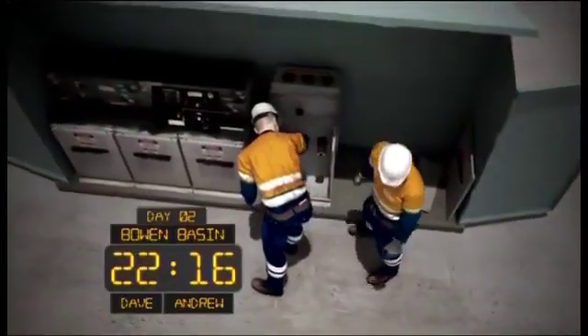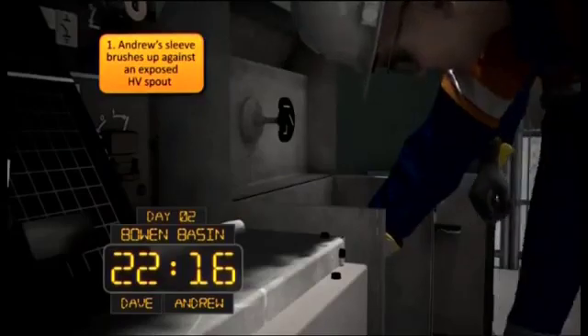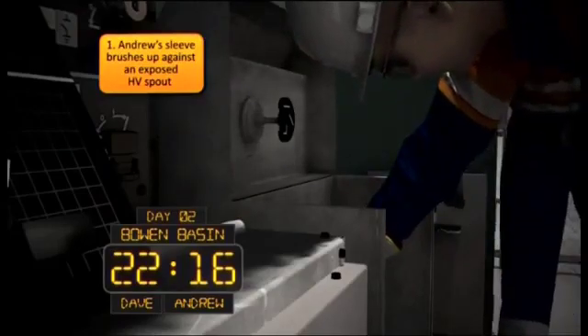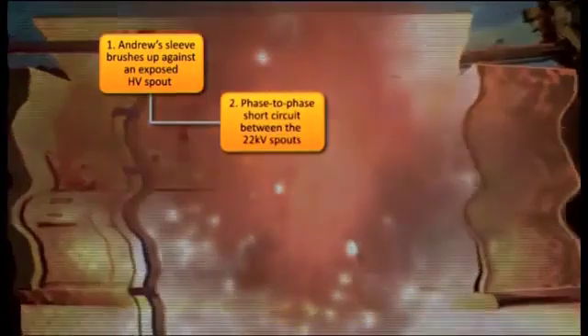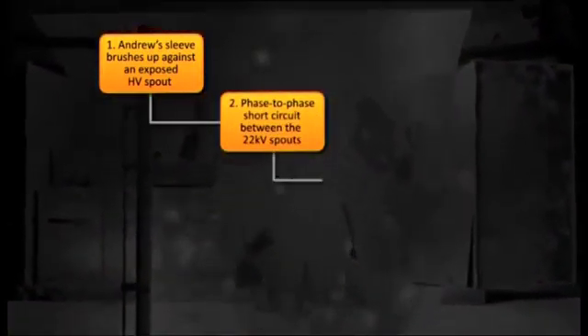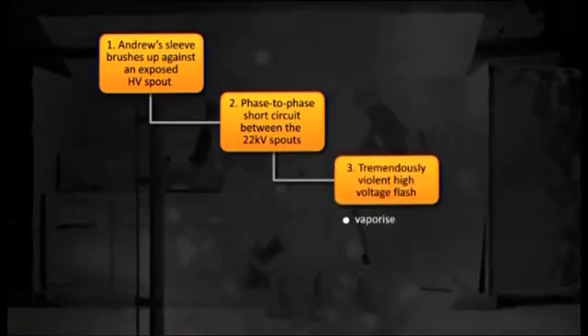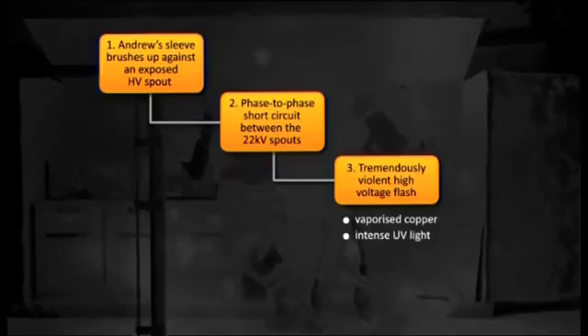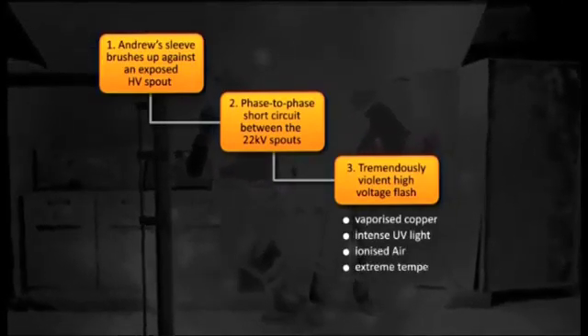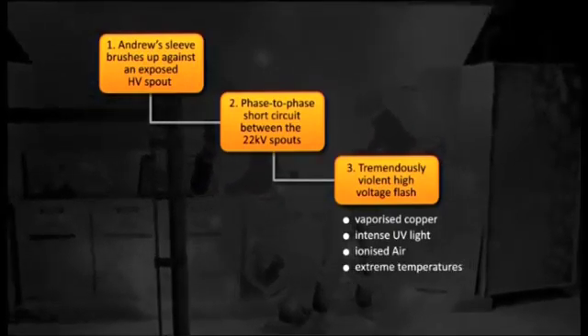What has just happened? What caused the explosion? Let's step it back and try and view this in slow motion from a different angle. We can now see that Andrew's sleeve brushes up against one of the exposed high voltage spouts, creating a phase-to-phase short circuit between the 22 kV spouts. This results in a tremendously violent high voltage flash that instantly fills the air with vaporized copper, intense UV light, ionized air, and temperatures of thousands of degrees centigrade.